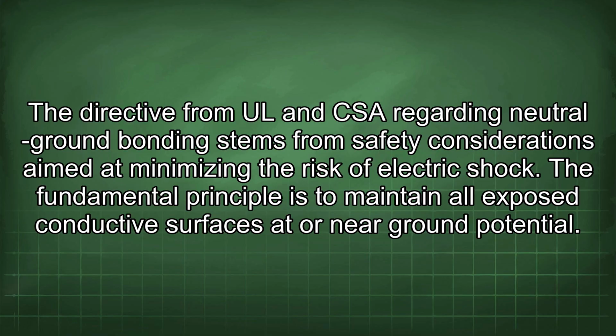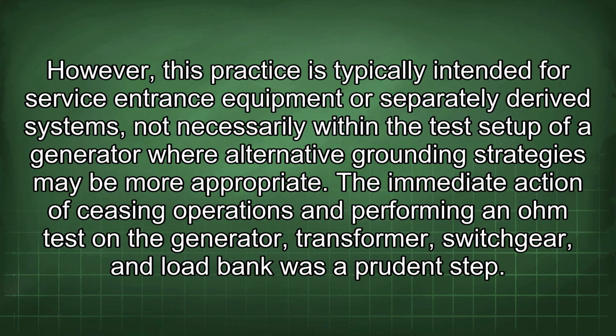The fundamental principle is to maintain all exposed conductive surfaces at or near ground potential. However, this practice is typically intended for service entrance equipment or separately derived systems, not necessarily within the test setup of a generator, where alternative grounding strategies may be more appropriate.